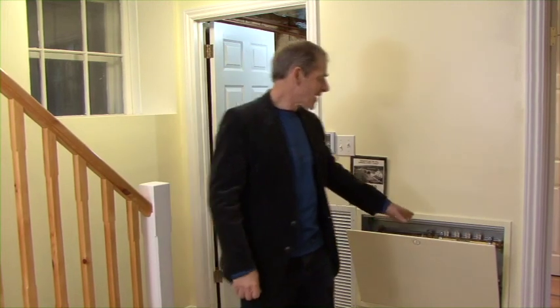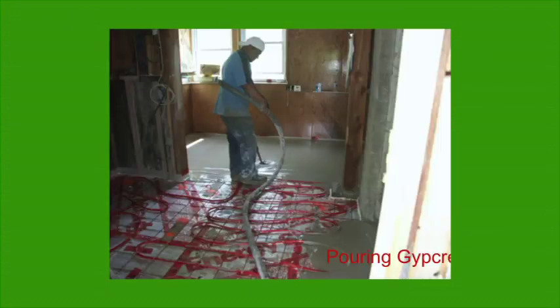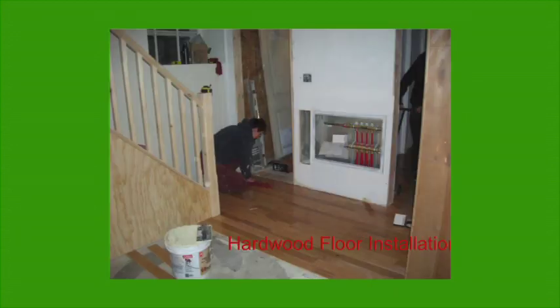We're here by the floor heating manifold that connects to tubing in the floor. We wanted to insulate this slab-on-grade floor, which is very cold in the winter and damp in the summertime. So after we had insulated it and were planning how to finish the floor, we thought we might as well put floor heating tubing in it while we had the floor under construction. So there's a 1/2-inch plastic PEX tubing laid on top of 1.5 inches of rigid foam insulation sheeting, and that's embedded in 1.5 inches of gypsum overpour flooring, leveling layer, and then covered with the engineered hardwood floor.